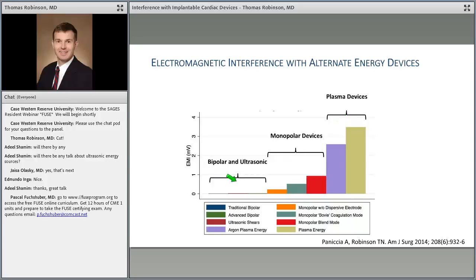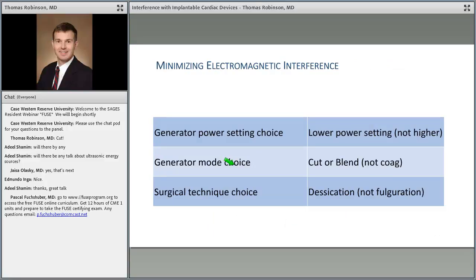But the best devices, if you could preferentially use a traditional bipolar device, which has very low voltage, or an advanced bipolar device, which typically has tissue sensing as part of how the device works. So bipolar, and the other one is ultrasonic that Jason just talked about. Ultrasonic devices really don't give off any electromagnetic interference. Their cords do have some electromagnetic interference, but once it hits that piezoelectric electrode in the handle, there's no more electromagnetic interference down that shaft. So preferentially, if you could use those, that would be a good idea.